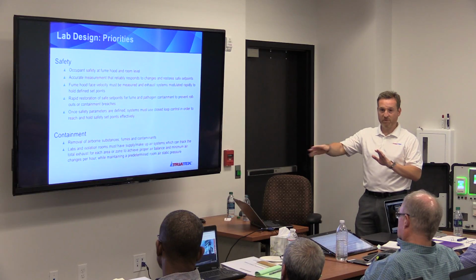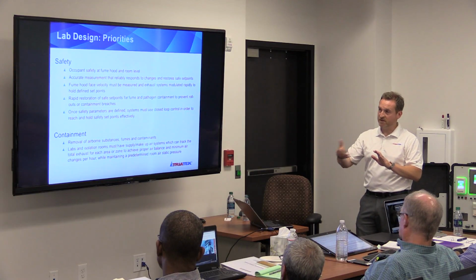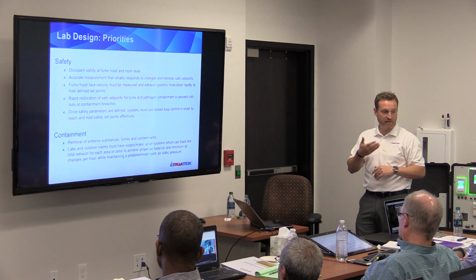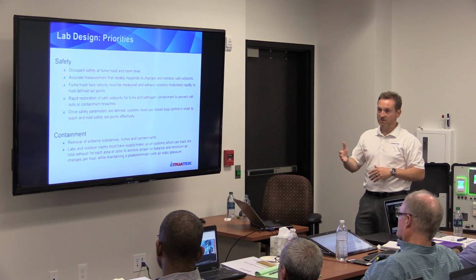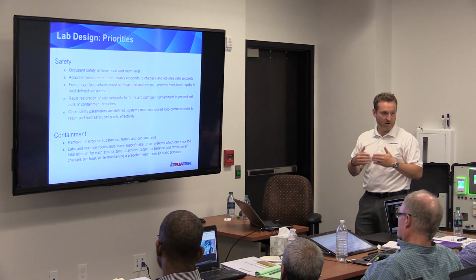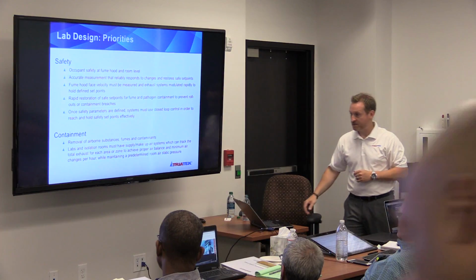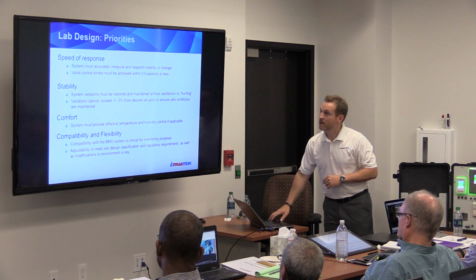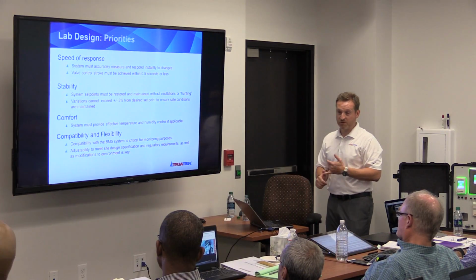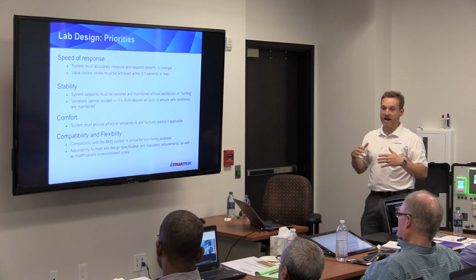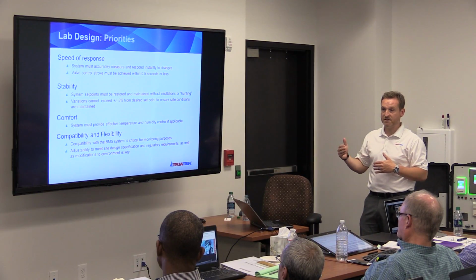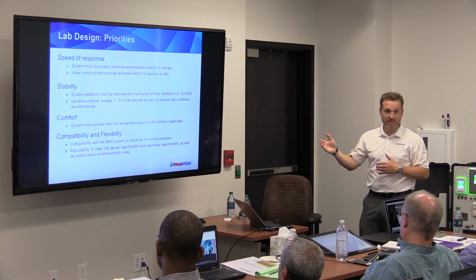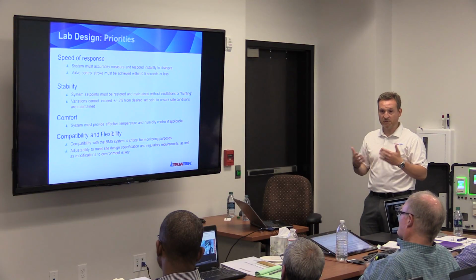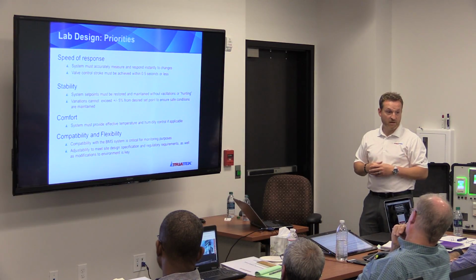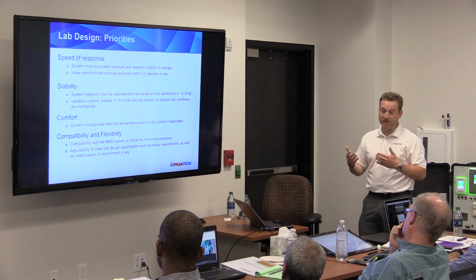Containment is also obviously a design priority. At the fume hood level, we make sure that we're removing all of the contaminants from the fume hood so that the contaminant is not getting to the end user's breathing zone. And then also the room itself has to be controlled to a positive or negative pressure depending upon the application. Speed of response is critical. Systems must accurately measure and respond instantly to changes, typically within half a second. So we're using these PID loops and these controllers that can control in a high-speed manner.